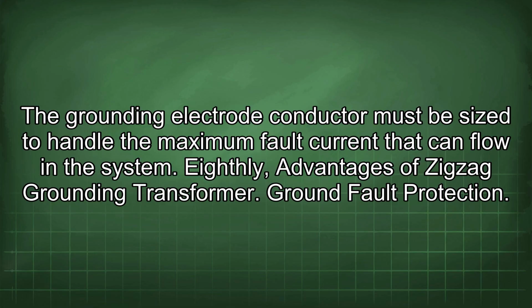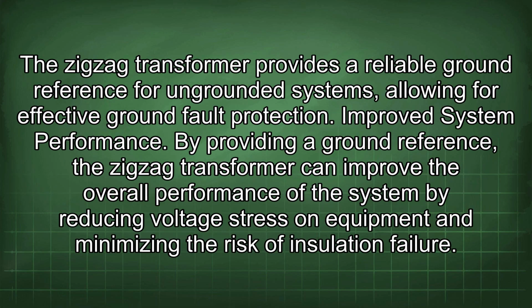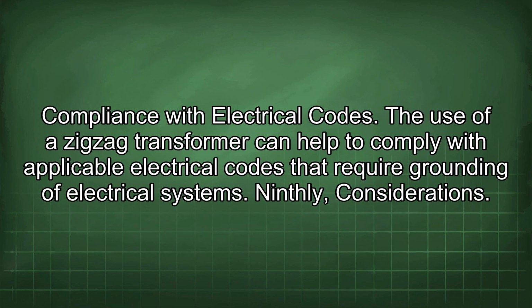Eighthly, advantages of zigzag grounding transformer. Ground fault protection. The zigzag transformer provides a reliable ground reference for ungrounded systems, allowing for effective ground fault protection. Improved system performance. By providing a ground reference, the zigzag transformer can improve the overall performance of the system by reducing voltage stress on equipment and minimizing the risk of insulation failure. Compliance with electrical codes. The use of a zigzag transformer can help to comply with applicable electrical codes that require grounding of electrical systems. Ninthly, considerations.